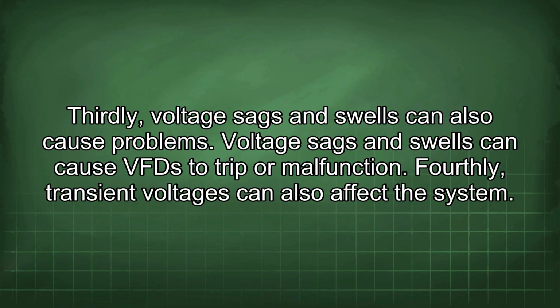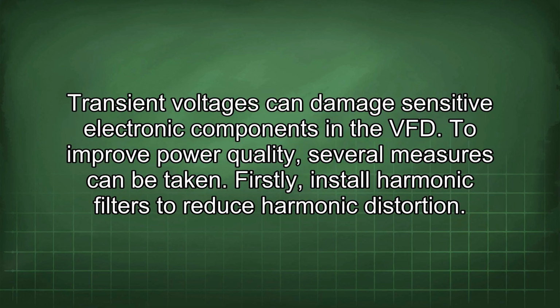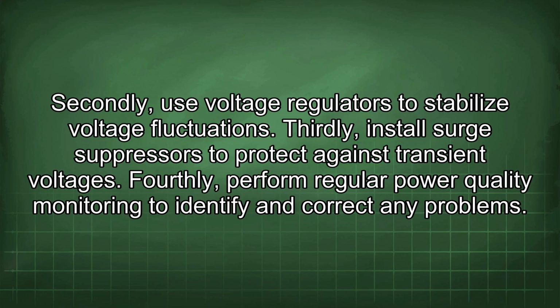Thirdly, voltage sags and swells can also cause problems. Voltage sags and swells can cause VFD to trip or malfunction. Fourthly, transient voltages can also affect the system. Transient voltages can damage sensitive electronic components in the VFD. To improve power quality, several measures can be taken. Firstly, install harmonic filters to reduce harmonic distortion. Secondly, use voltage regulators to stabilize voltage fluctuations. Thirdly, install surge suppressors to protect against transient voltages. Fourthly, perform regular power quality monitoring to identify and correct any problems.